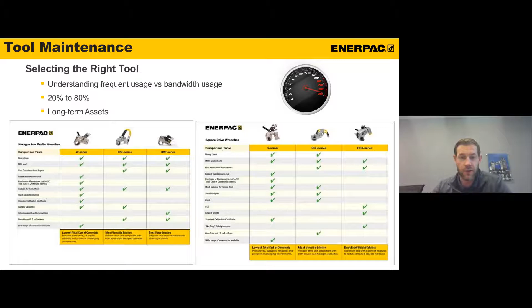On the calibration front, we have certifications and ongoing checks. It very much depends on your site needs and what the asset owner is telling you. Some asset owners require 3-month calibrations, some require 6-month, some 12-month. It depends, so we want to be open to whatever that asset needs, since the asset owner is ultimately the customer in this circumstance. We want to make sure those tools are operating as effectively as possible. I use the torque wrench as the example, but this can apply to any of the industrial tools out there.